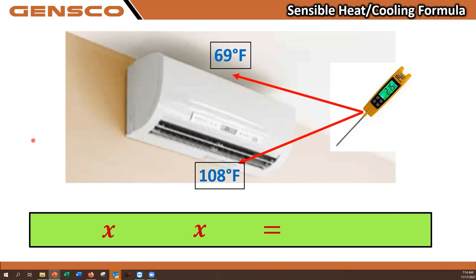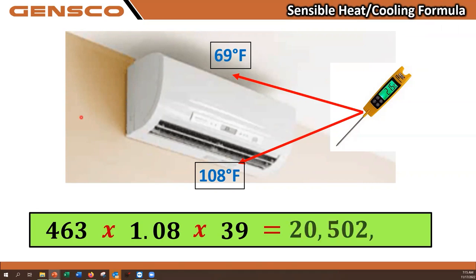This is our results. We have a 69-degree return air and a supply air of 108 degrees. The difference of those numbers is 39 degrees. We're going to put that in our formula. From our submittal, our CFM was 463 CFM. We have our constant of 1.08, and our temperature difference, our delta T, was 39 degrees. We put that formula together and it results in a BTU-H output in heating of 20,502 BTUs.